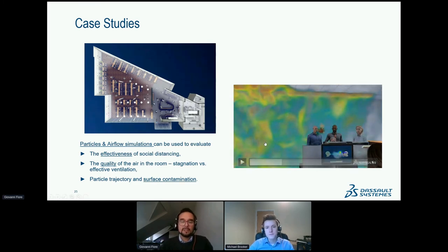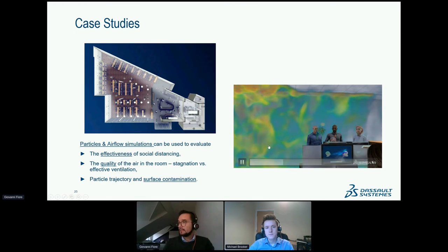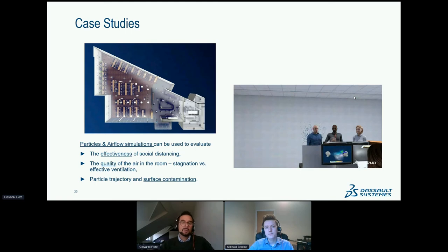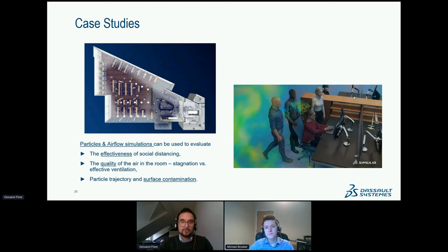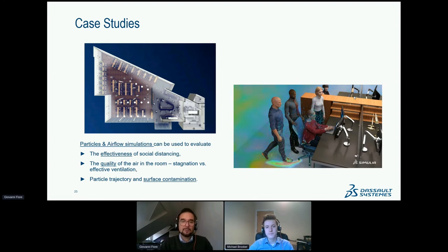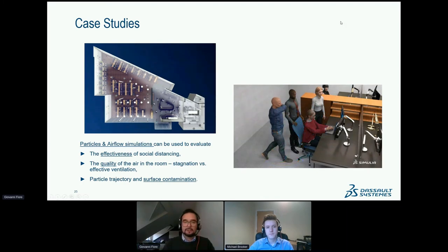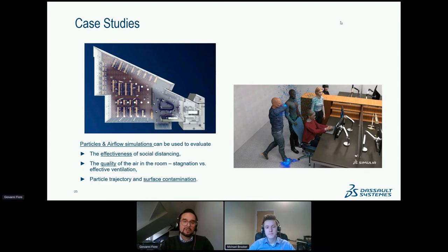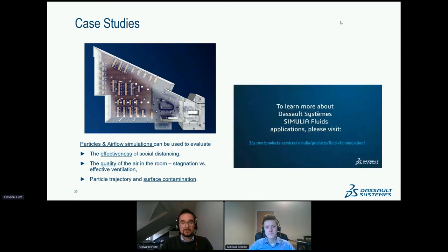A similar application was run for an office, with the HVAC system operating as a standard working day and a person coughing into that environment. We wanted to show how social behavior affects the particle footprint — both in terms of where particles land and in what quantity. Simulating the person coughing without covering their mouth versus covering their mouth showed a dramatically different result: covered, the cloud traveled far less far and the floor footprint was much narrower. This also captures surface contamination, not just airborne.